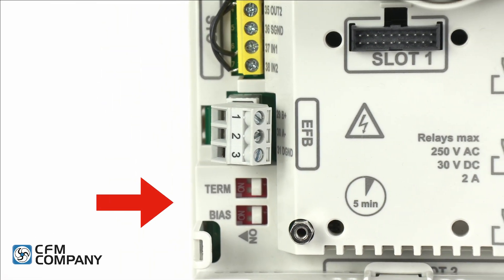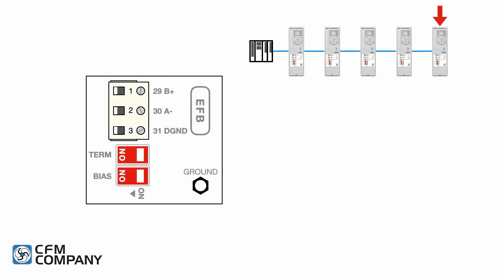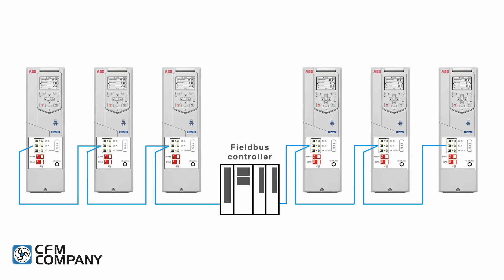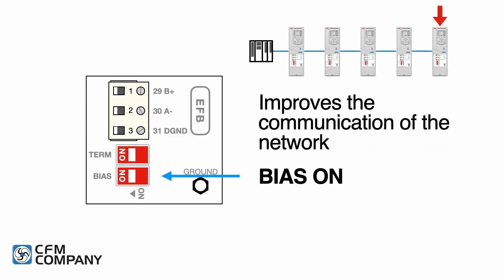Terminate the shield only at the ground terminal in the building automation controller. The ACH 580 includes both a termination switch and a bias switch below the EFB terminal. If the drive is at either end of the network, set the termination switch on — this adds an end-of-line 120 ohm resistor to the end of the network. One device, preferably at either end of the network, must have the bias switch on. The bias switch can help improve the communication of the network.